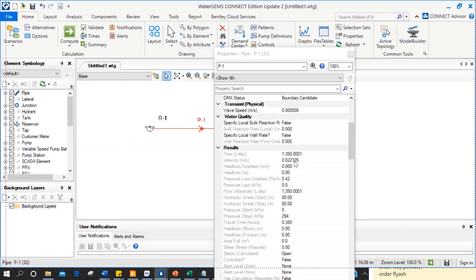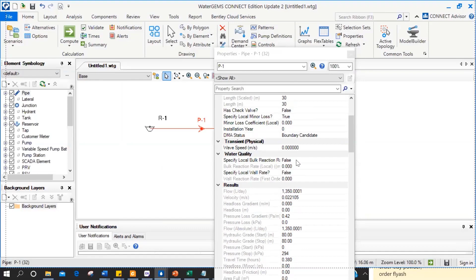So we'll run it again. Now see, the velocity has increased. If you decrease the size of the pipe, the velocity will increase. If you increase the size, the velocity will decrease. Another important term is head loss gradient. How much head loss is happening in 1 meter? For this, the unit we keep generally is meter per kilometer. A general convention is that we keep the head loss gradient at 5 meter per kilometer. The head loss should not be more than 5 meter per kilometer. It can be more or less, but it is a general convention. It is not written anywhere, but it is a general practice.